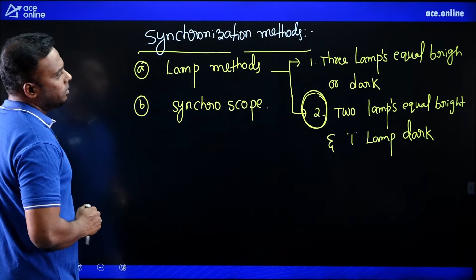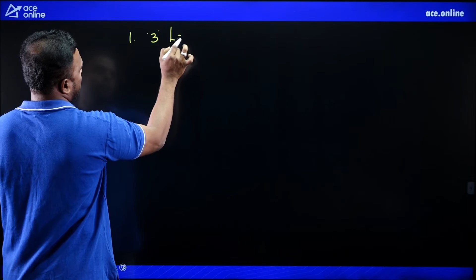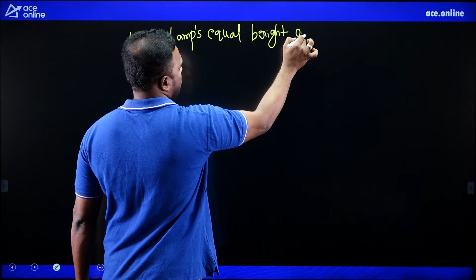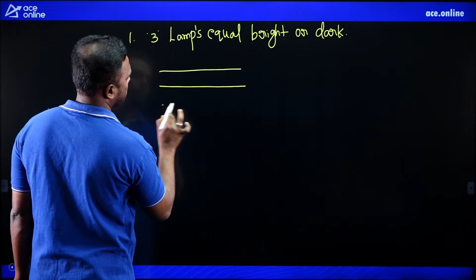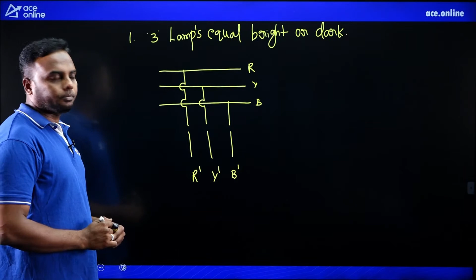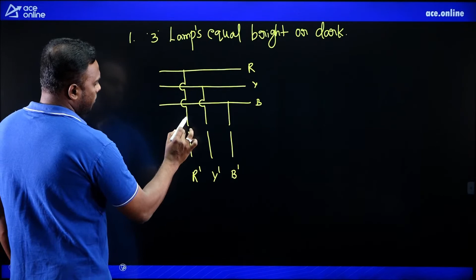Now let's see the first one, 3 lamps equal bright or dark. What we need to do here is take 3 lamps. This is the bus bar 3 phases, R phase, Y phase, B phase, and this is the alternator 3 phases, as in the previous diagram: R dash, Y dash, B dash. Now we have to connect 3 lamps such that L1 is connected between R and R dash, L2 is connected between Y and Y dash, and L3 is connected between B and B dash.